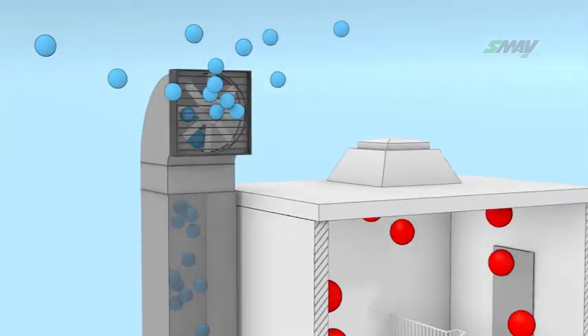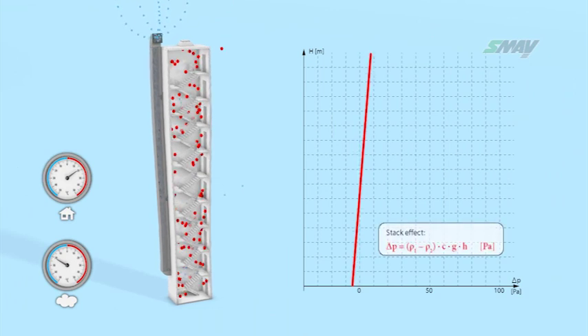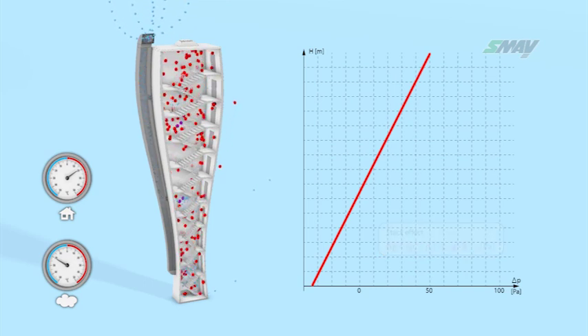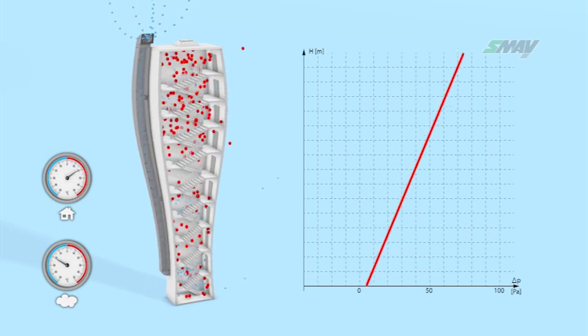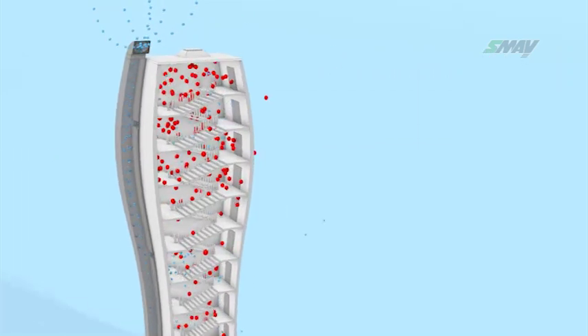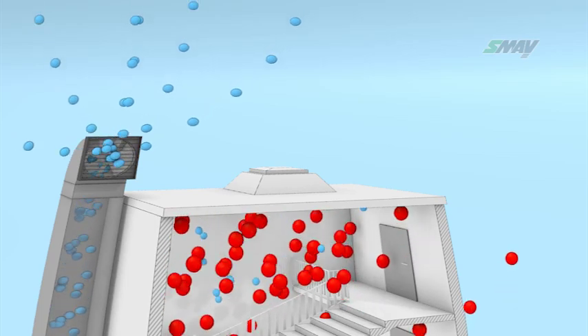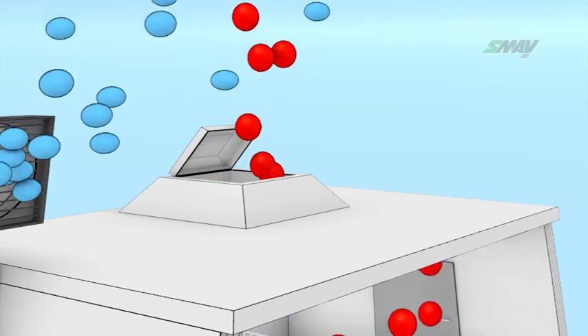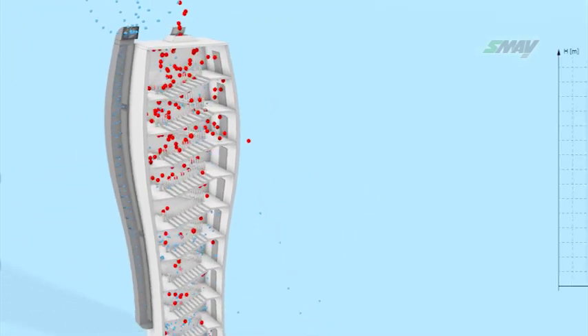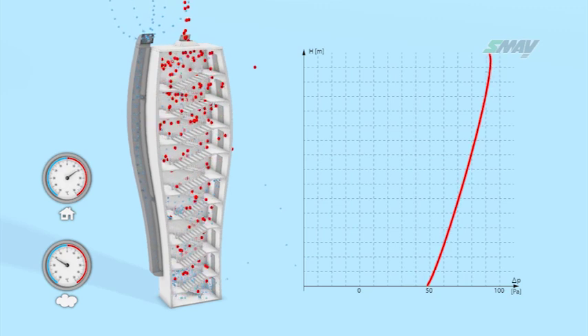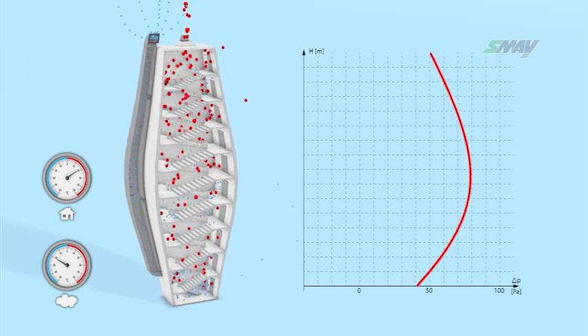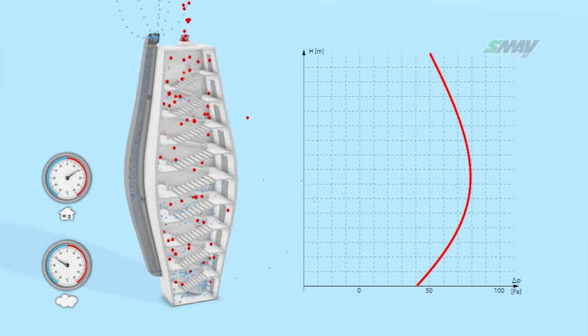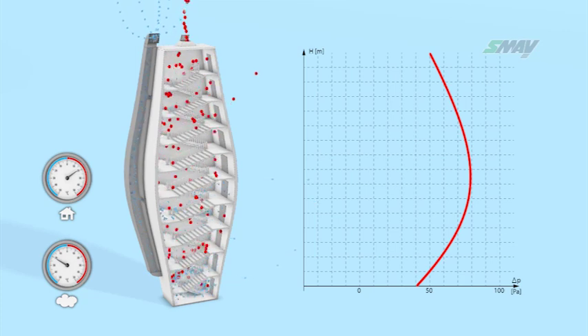However, if in this case air is supplied to the stairwell at a temperature significantly below that of the inside, then pressure stratification will occur as a result of the stack effect. The supply of large amounts of air causes a rapid increase in pressure, but the increase will not be uniform across the entire height of the stairwell. The stack effect will disturb its distribution. A pressure increase in the upper parts causes the barometric overpressure dampers to open, maintaining pressure at no more than 50 pascal. Once the barometric overpressure dampers open, pressure in the entire stairwell changes and its value equals the resultant of the flow resistances, relative to the size of the airstream and the stack effect.